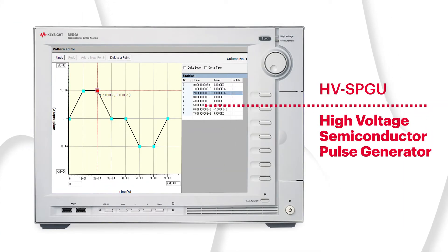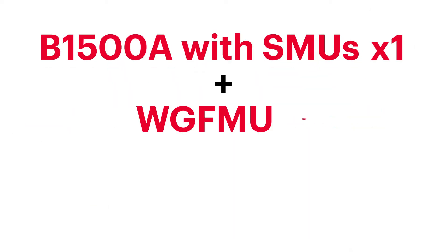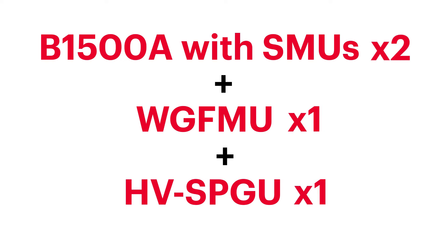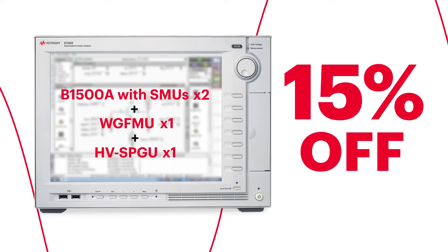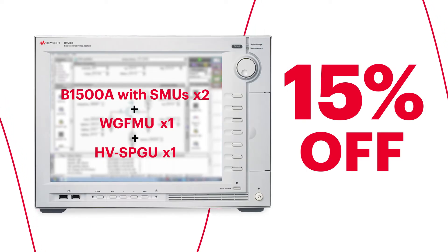The High Voltage Semiconductor Pulse Generator, or HVSPGU, can output a maximum of ±40 volts with 3-level pulsing and arbitrary waveform generation capabilities. When you order the B1500A with two SMUs, WGFMU, and HVSPGU, you can save up to 15% off the price compared to purchasing the same items separately.